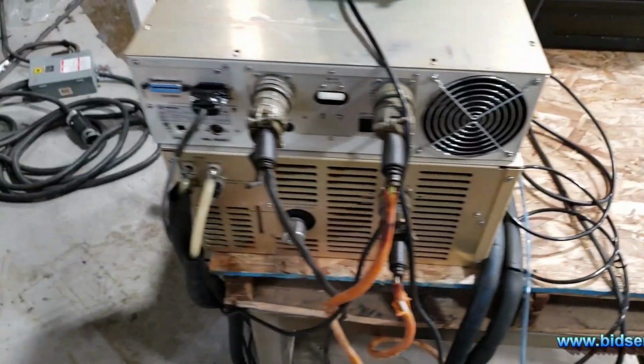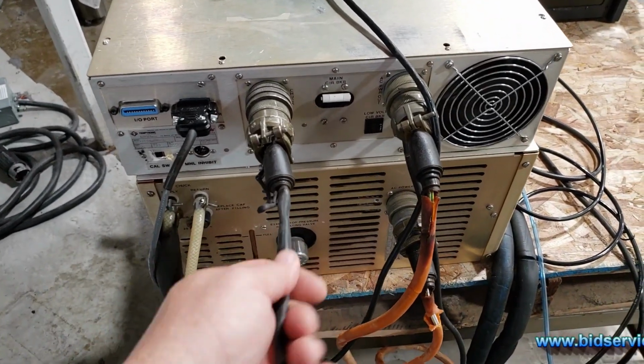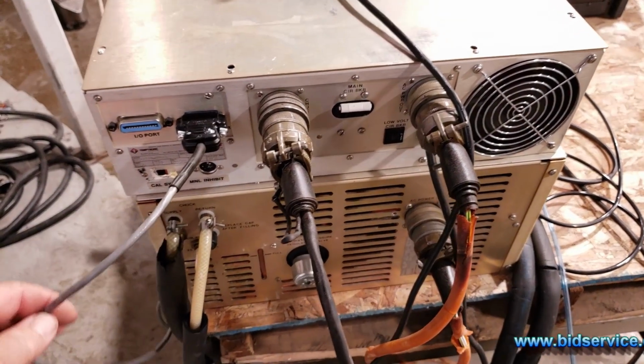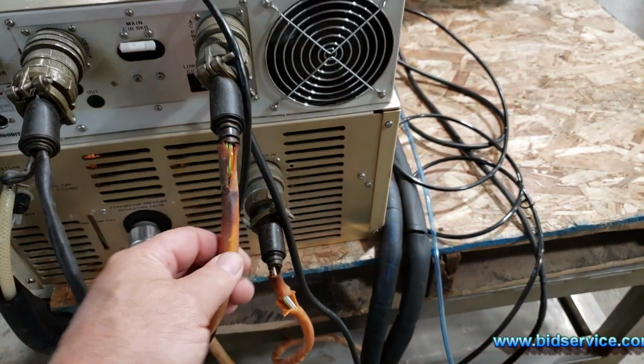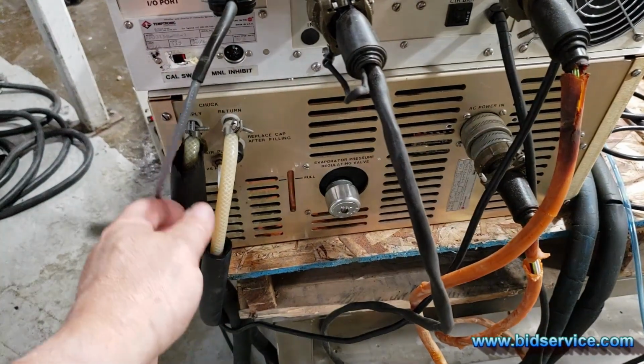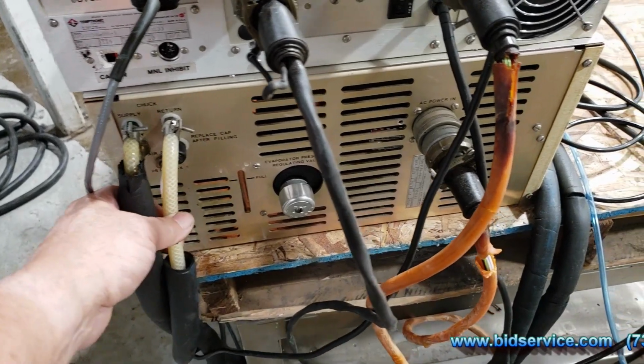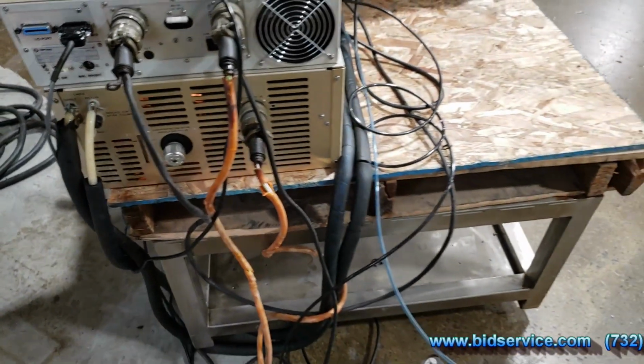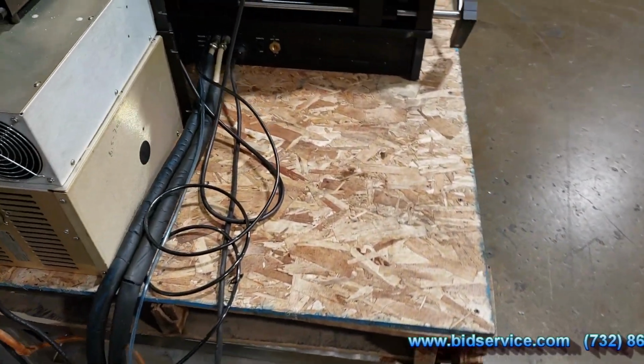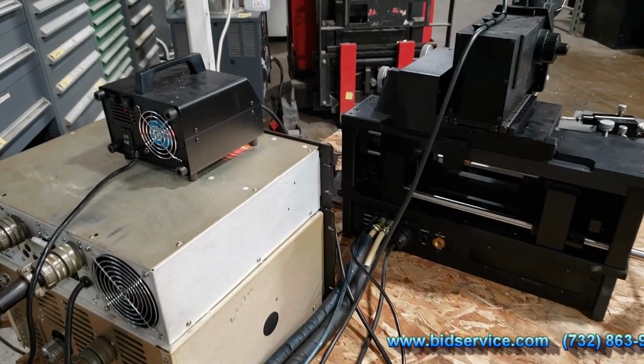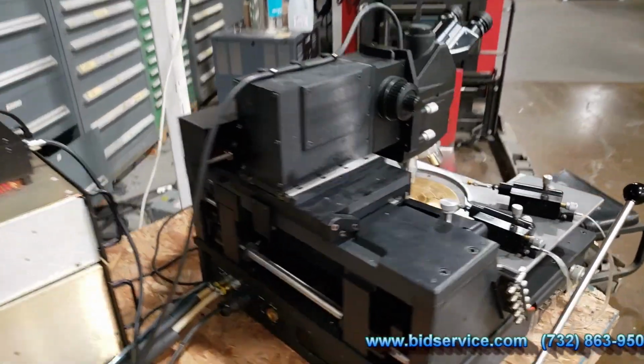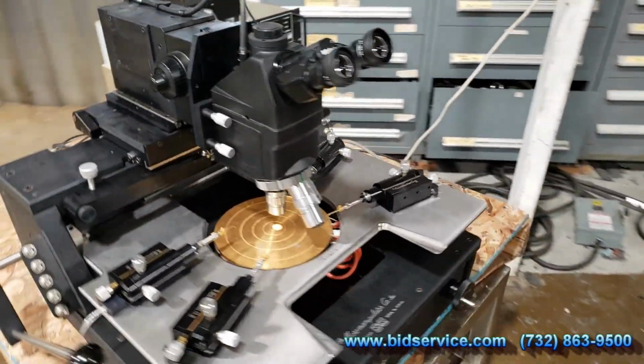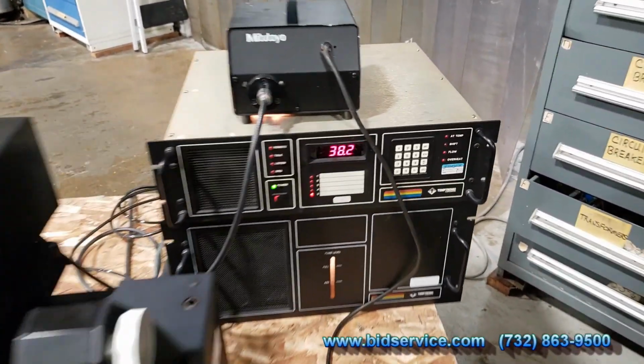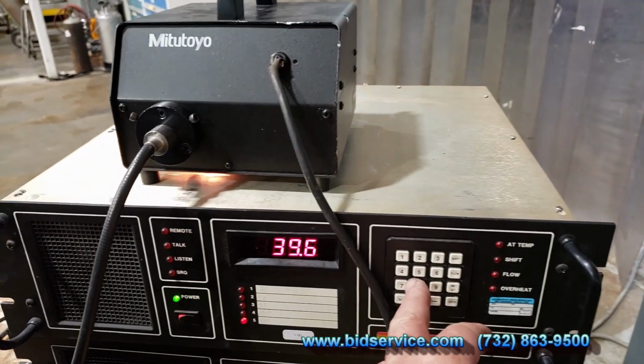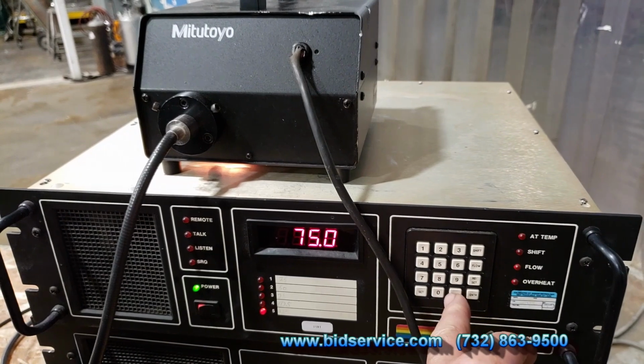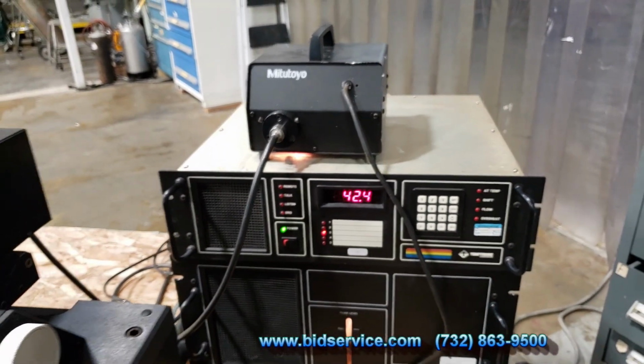Now on the back of the Temptronics, you have the connection for the chuck, then you have this one for the jogger, and then you have your interconnect cable here. And on the bottom unit you have your chuck coolant lines. So as you can see, the system is going up in temp. If we want to see it regulate, we'll just put it at one that we can see it go to temperature.